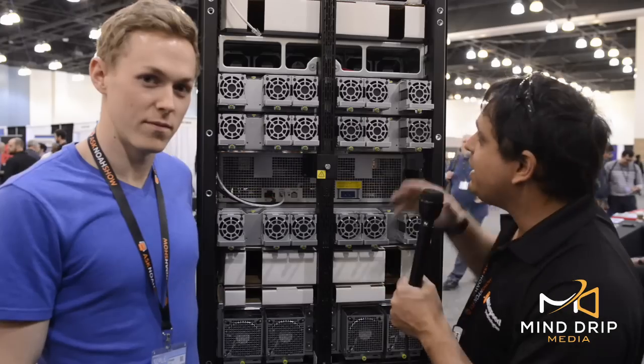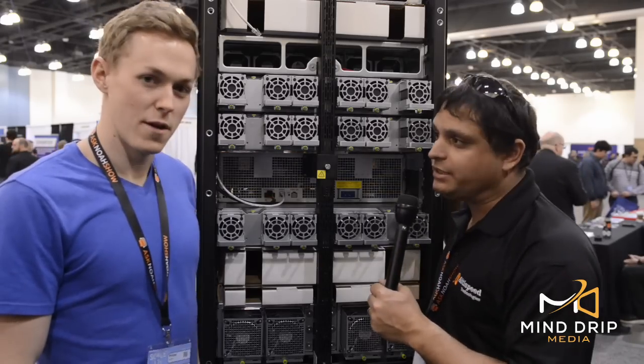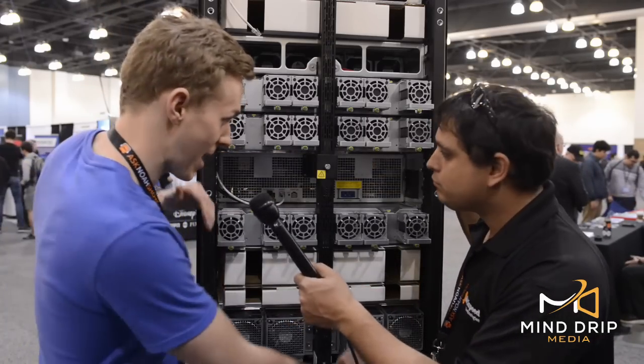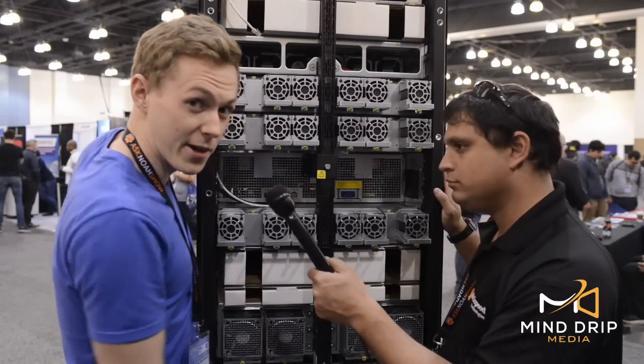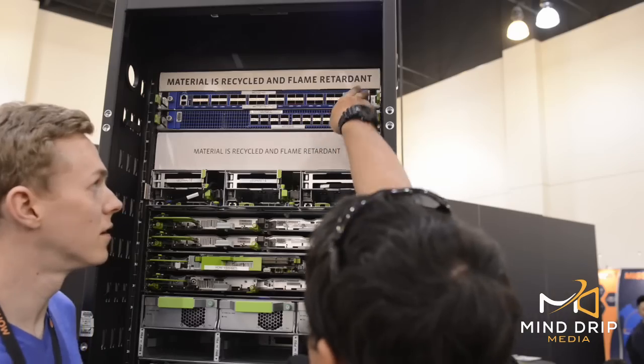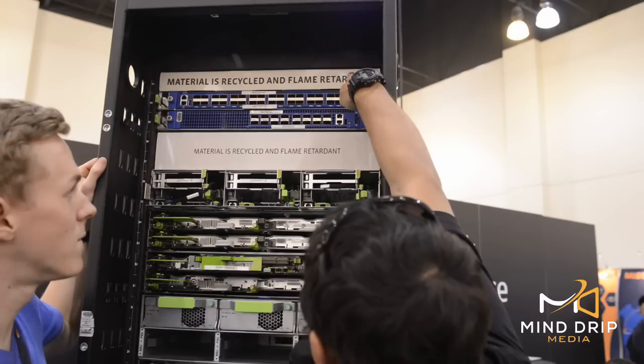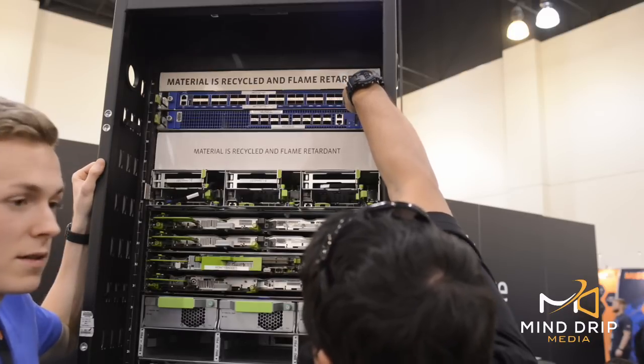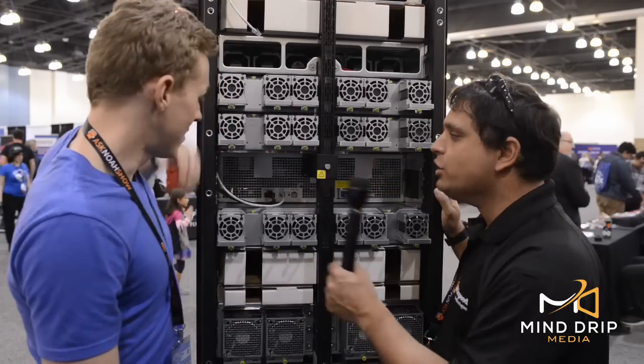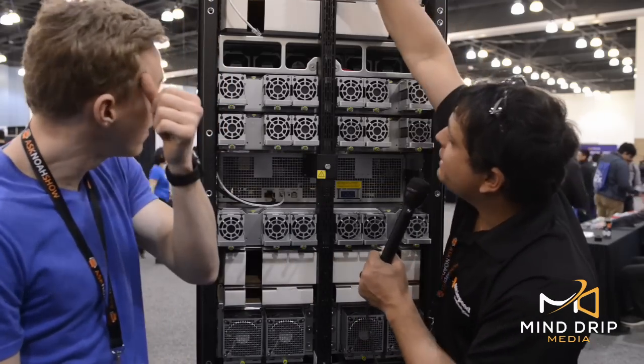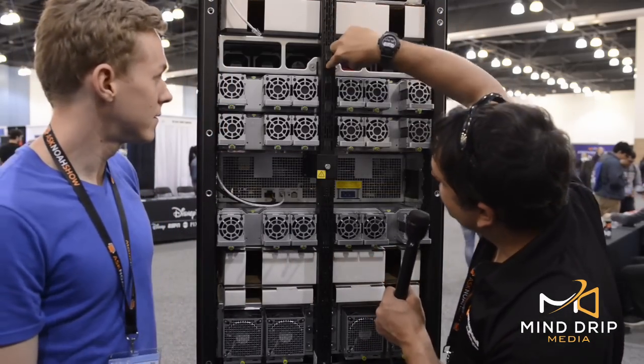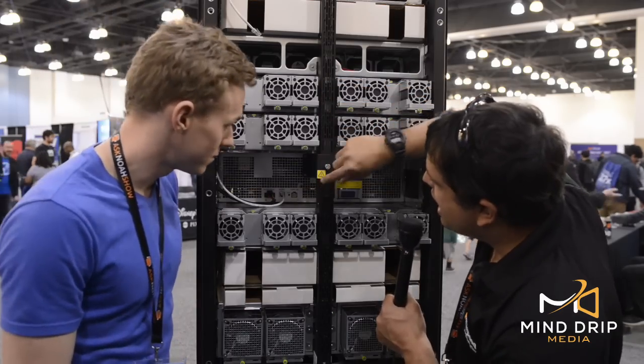Let's start with the actual design of the rack itself. Now, the rack is a different dimension than your standard 19-inch rack. That's right. If you look at this rack, it's actually 21 inches wide. You'll get a better shot from the front, where you can see they've installed switches that are 19-inch compatible but have little expanders to fit the 21-inch rack. The rack itself has this back plane, and inside of this you can see there are two silver bars, and those are providing 12-volt power to the entire rack.